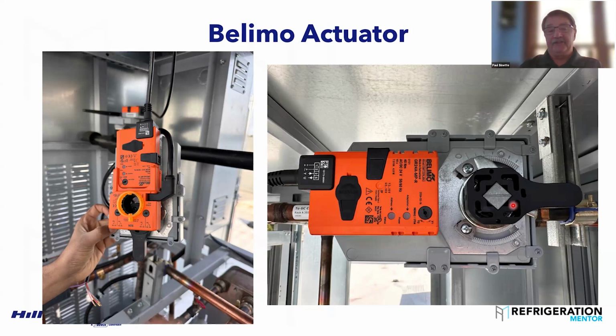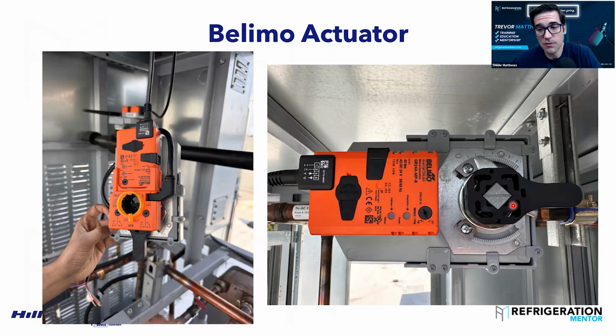Because when I'm going into split condenser, I want the split condenser valve to be fully shut before I allow the pump down line to open. Because if you start these two together without a delay, then as we're closing and reopening the split condenser, we're going to overpressurize the vessel. Yeah, and we don't want that.